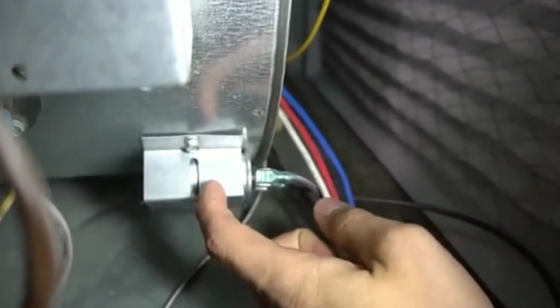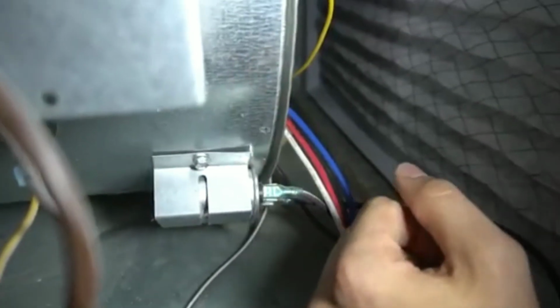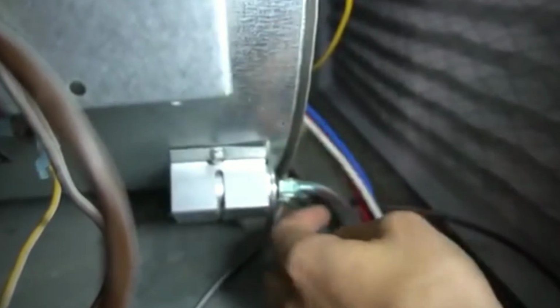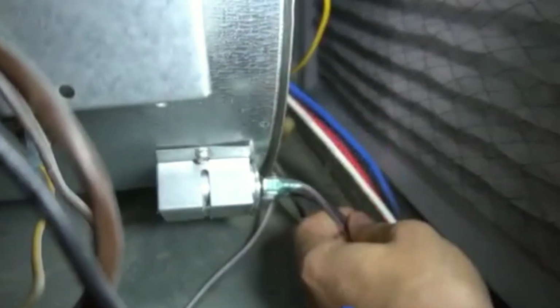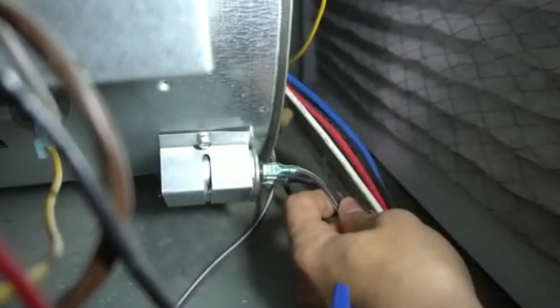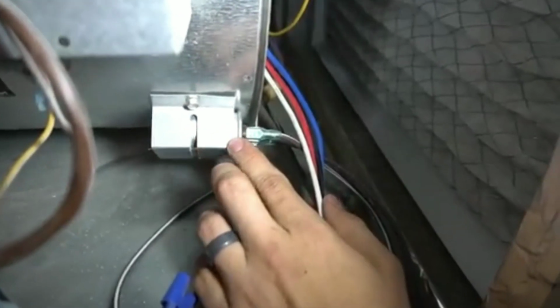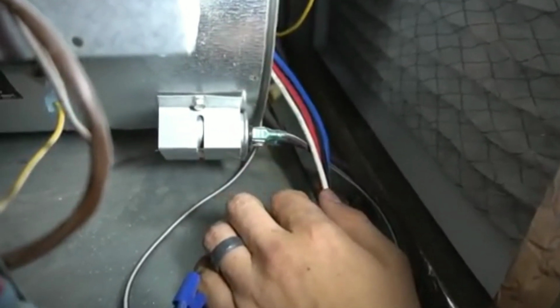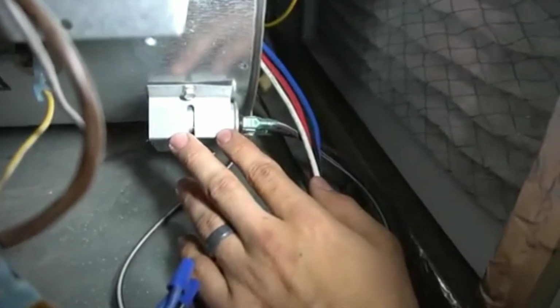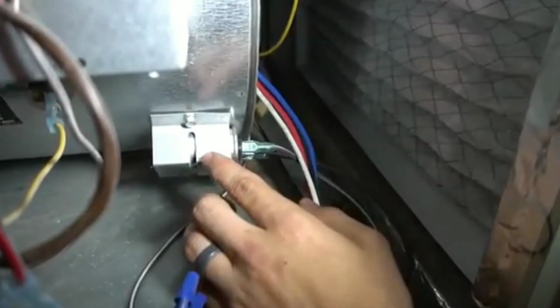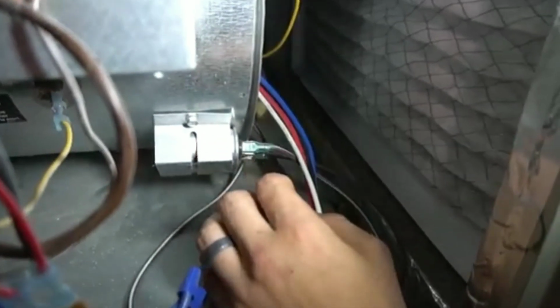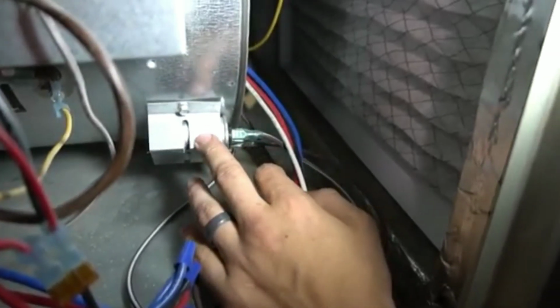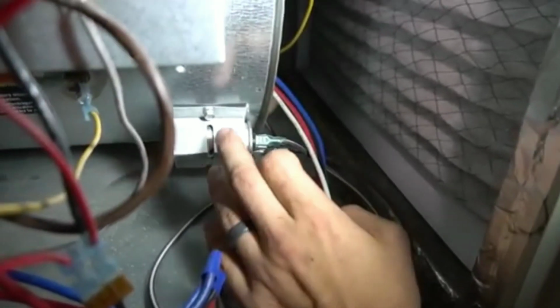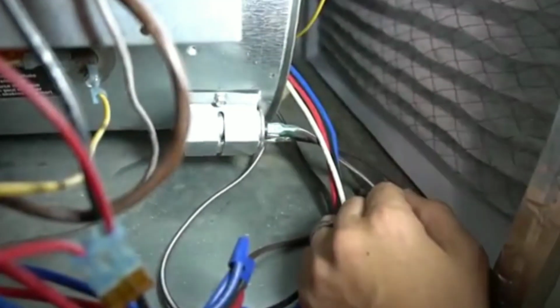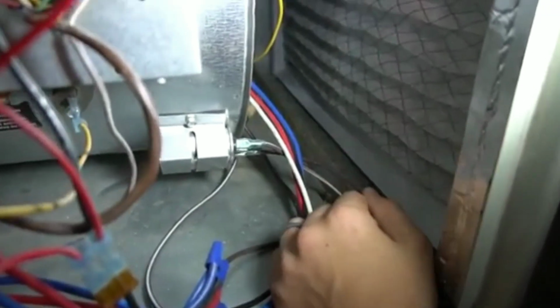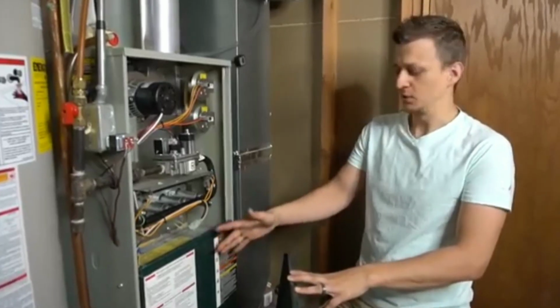If it's really weak or dead, that blower motor will not turn on. So if you have a meter, as preventative maintenance, you can check your capacitor and make sure it's rated good, and that the readings are within spec. And these capacitors aren't too expensive, so it would be a good idea as preventative maintenance to have one of these as a backup along with the dual capacitor. So if they ever go out on you on a really hot day or a really cold day, you can just swap them out with that extra you have and be good to go. So that's all you have to check on the blower motor.